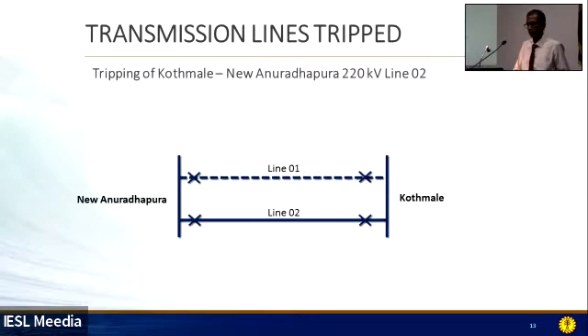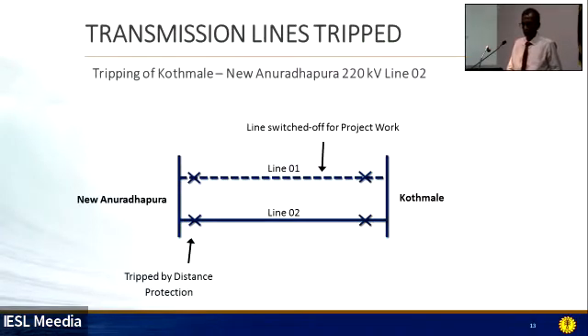Next, I will discuss the tripping of this Kotmale New Anuradhapura line. In the New Anuradhapura Kotmale double circuit line, one line was taken out for project work, and only line 2 was available on the day of the total failure. After tripping of Kotmale Biyagama lines 1 and 2, all the power from the Mahaveli power plants to the rest of the network went through this line 2, and severe power oscillations were observed in that line. In that process, from the digital disturbance record we observed a low voltage level and high current level, and the distance relay operated because of that low voltage and high current situation.